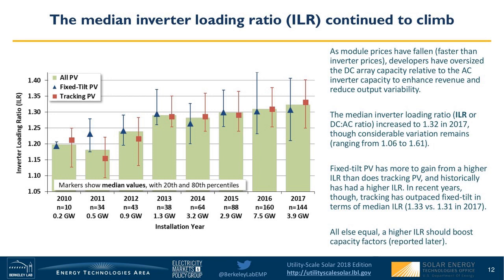And especially if we go into a future where we will have more storage that is DC coupled directly to the modules, one could make the argument that those storage units could then absorb some of the energy that would otherwise be clipped during peak times, and that would then enable an even higher inverter loading ratio. Some people use up to maybe 1.9 even.